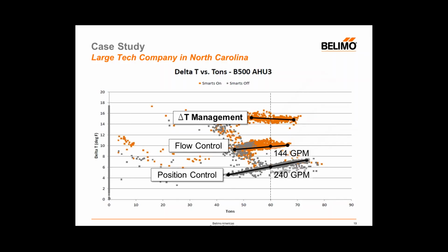And then when we put delta T management in place, we're now down under 100 gallons a minute. So 96 gallons a minute, where we started at 240 gallons a minute, to cool the same space the same amount with the same equipment. So we used 40% of the original volume of water to cool the same space the same amount. And so that's why we're really excited about this technology.